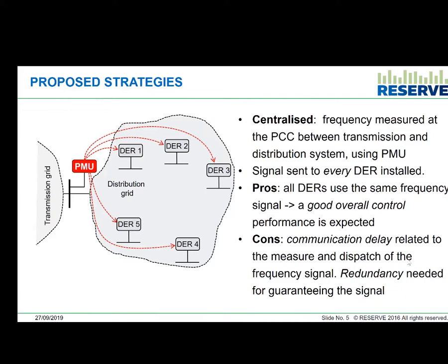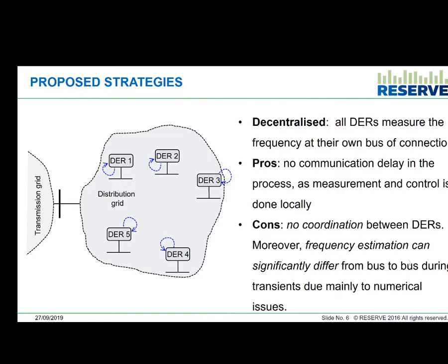The second strategy is the decentralized one. In this case, all measurements are made locally — every distributed energy resource has its own measurement at that point. There is no communication delay, because we use the measurement made exactly at that place. However, there is no coordination between the distributed energy resources installed in the distribution system, and the frequency estimation can vary node by node due to the different properties of the network, and due to numerical issues in the tools used for estimating the frequency.